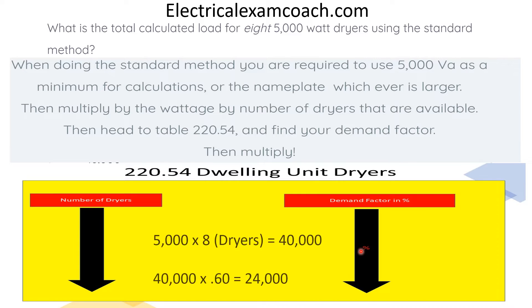Then we perform our math. We take our 5,000 per dryer, multiply it by our number of dryers. Then we take that total demand and multiply it by the demand factor. That gives us a new reduced load of 24,000 watts.